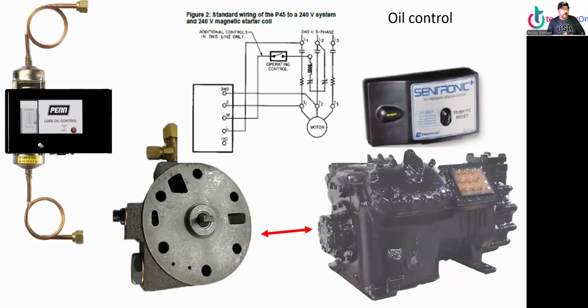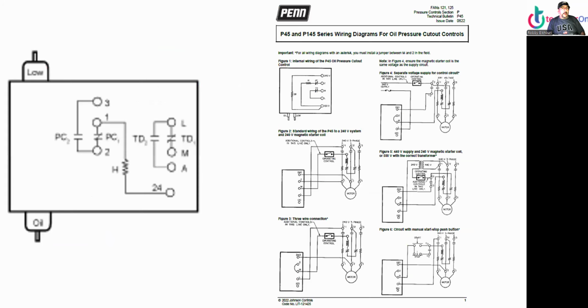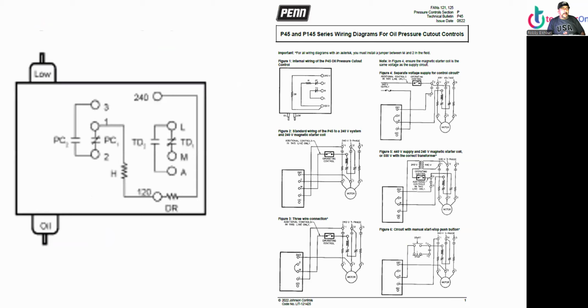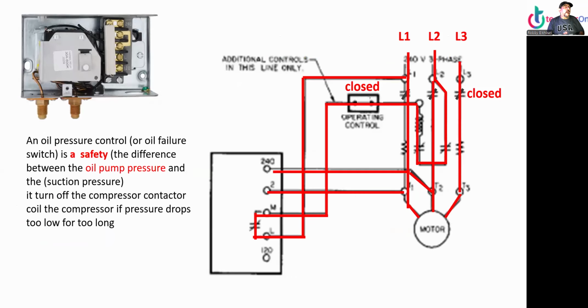Okay, now oil control. I'm going to cover this in detail. We have two kinds, the electronic and the regular. Bunch of diagrams. Alrighty, more diagrams, I'll cover them in detail. An oil pressure control, or oil failure switch, is a safety. It senses the differential between the oil pump pressure and the suction pressure. It turns off the compressor contactor coil if the compressor loses oil for a certain time, about 90 seconds. I'll cover it in detail. Now look at this diagram. How can you make any sense out of all this?